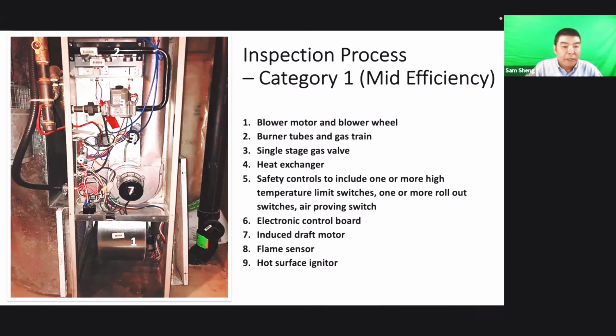If the pressure switch doesn't detect the inducer motor running, or for example the pressure switch has failed, then even if the inducer motor is running okay, there is still no signal to the control board. In that case the furnace will get the information that it cannot run the heat.